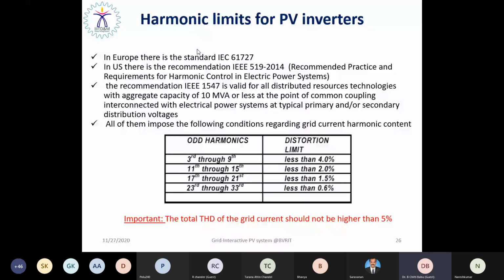Basically for harmonic limits on PV inverters, we use the IEC 61727 series, and in the US, Canada and the rest of the countries, we use the IEEE 519-2014 standard, which stands for the recommended practice and requirements for harmonic control in electric power systems. In addition to that, the IEEE 1547 standard can also be used for DER with a capacity up to 10 MVA.